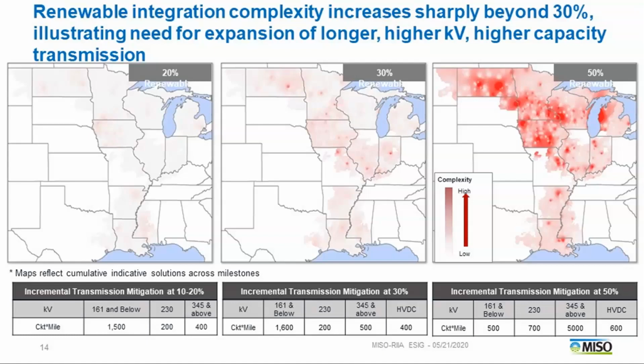These are the indicative types of solutions we're seeing were needed as more renewables come into the system. There's a crossover point as we go from where we're at today to 50% renewable penetration: initially we have a lot more transmission needs at the lower voltage around the point of interconnection of renewables, and as that share continues to increase, there's more of a widespread reliability impact, primarily thermal issues, along with some voltage issues, and the need to build out and connect wider areas to mitigate those issues, requiring higher voltage, larger solutions.